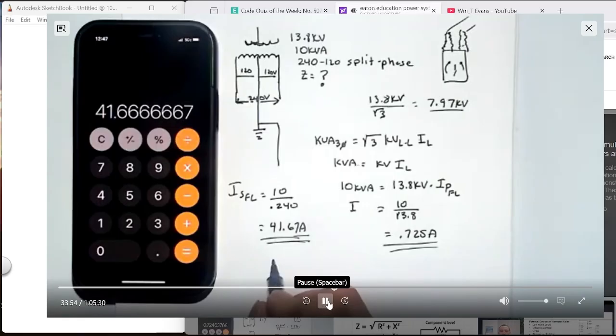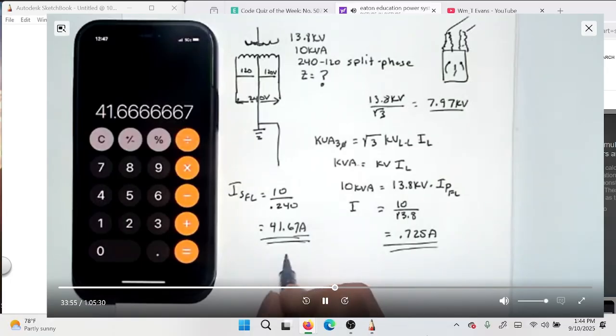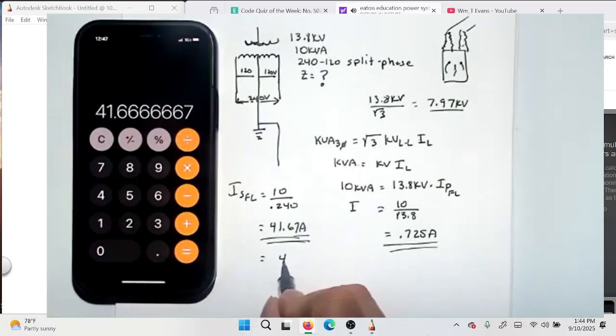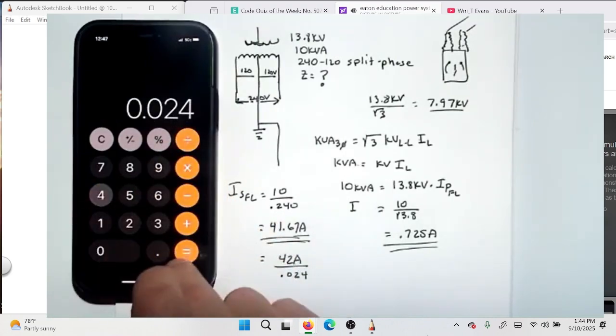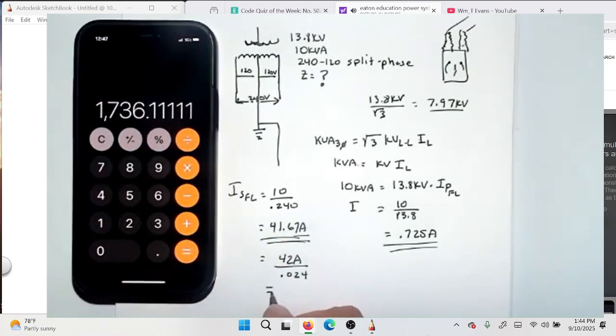Anyway, fault current. Let's just take that number, 42 amps, and divide that by our impedance. What is our impedance for this kind of transformer? I said it earlier, it's going to be between 2 and 3%. So let's just use, I think the one we showed was 2.4%. So push that number divided by 0.024, and we get 1,736 amps.